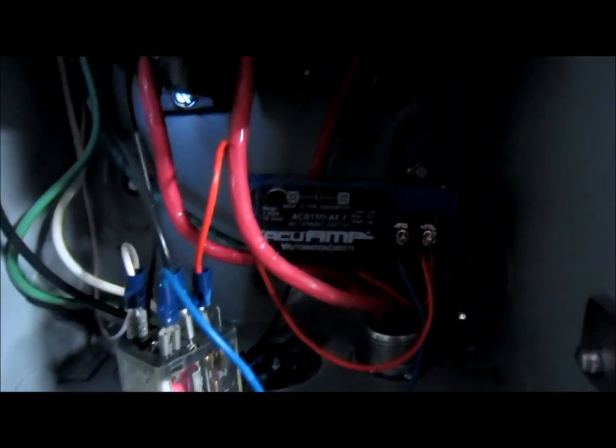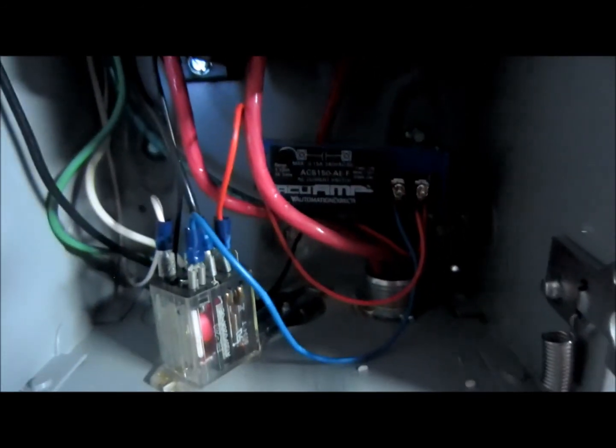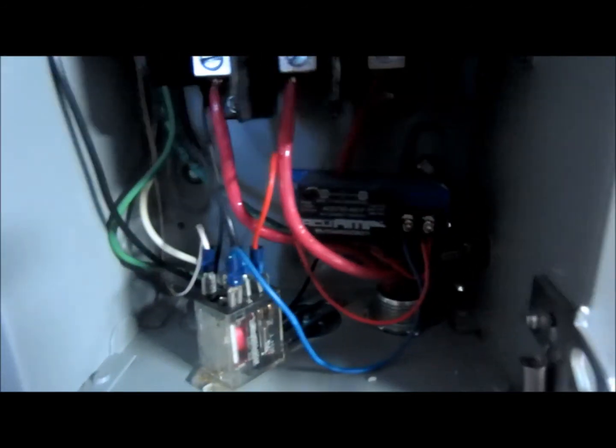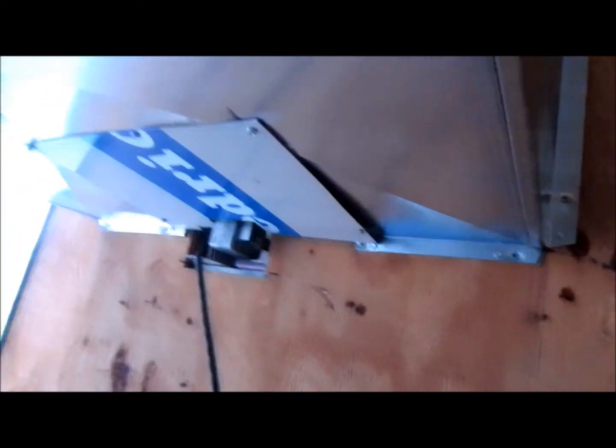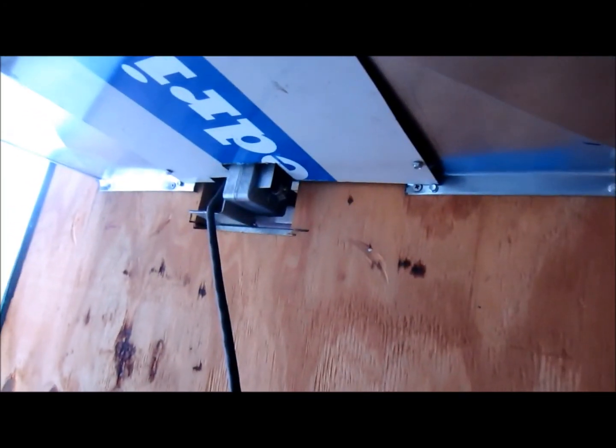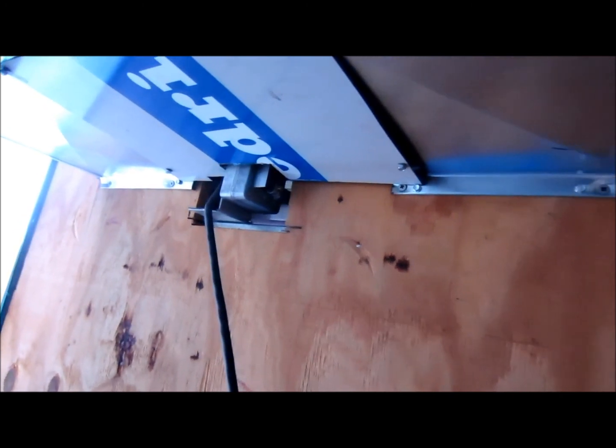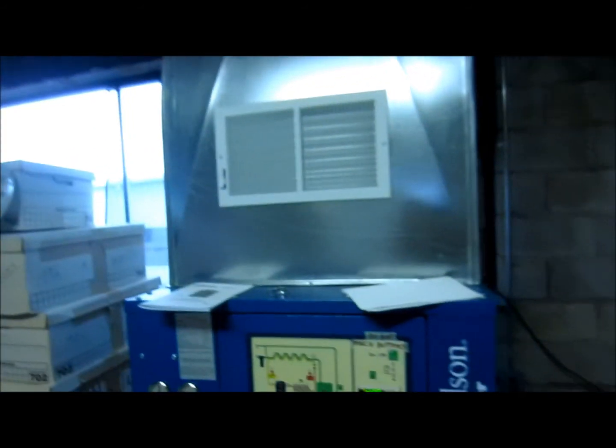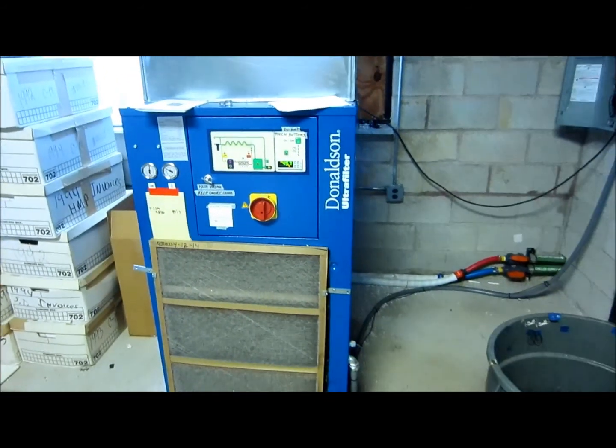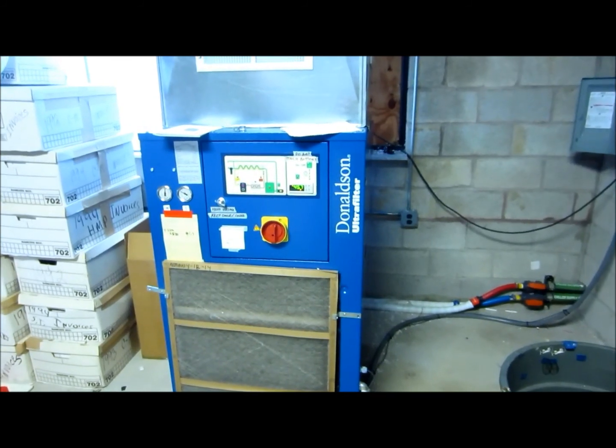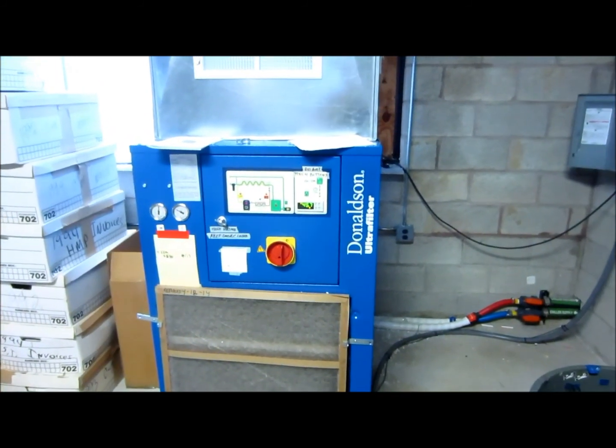This is an application using the AccuAmp current switch. It is controlling a small relay, which in turn operates a motor for the powered shutters on this chiller system. This room is basically for storage, except for this chiller, which is used for one particular piece of equipment.